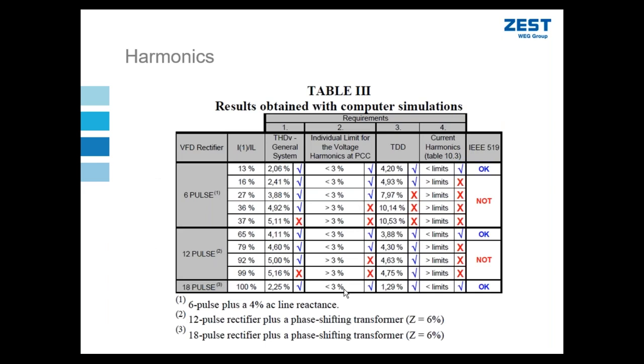Just to demonstrate that against one of the typical standards, IEEE 519, we did some experiments and some simulations. We took a plant scenario. We took a plant that's supplied by an 8 MVA utility transformer.